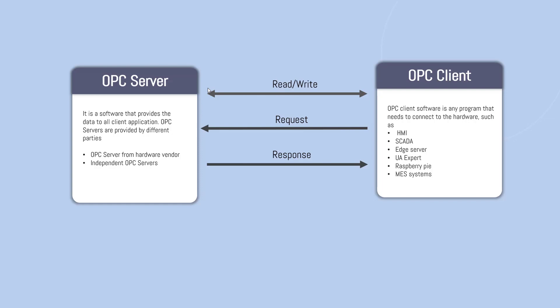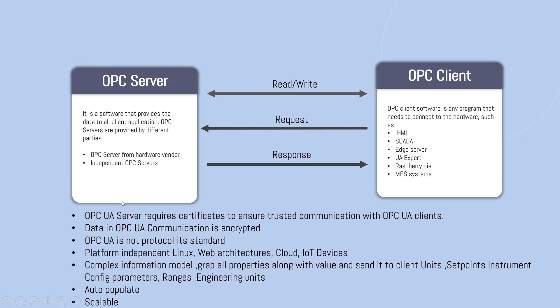What sort of actions are possible? Read and write. So OPC UA server requires certificates to ensure trusted communication between OPC UA clients. By that way, you are making sure the security feature as well. Data in OPC UA communication is encrypted. There is a big misunderstanding that exists nowadays that OPC UA or OPC is a protocol. It's not a protocol. It's a standard.